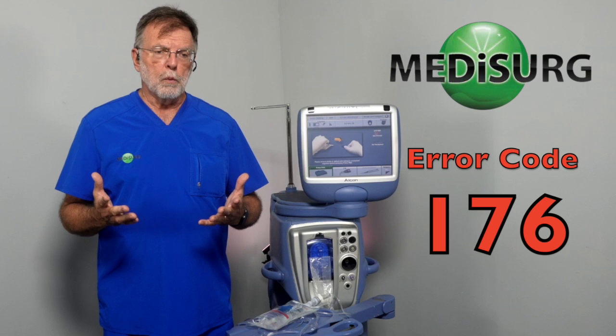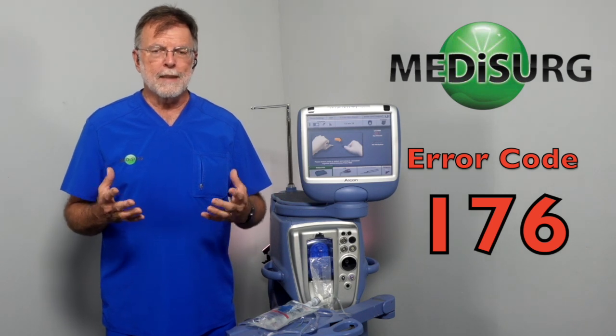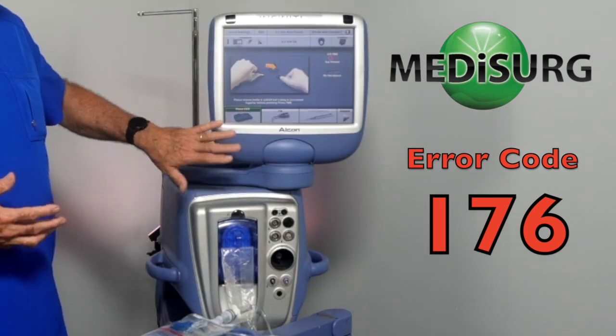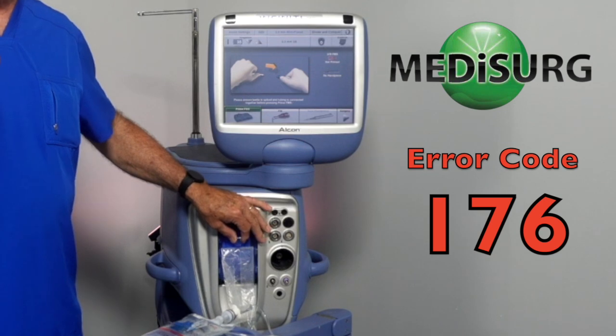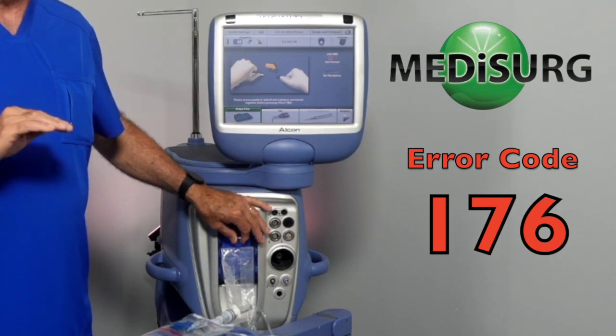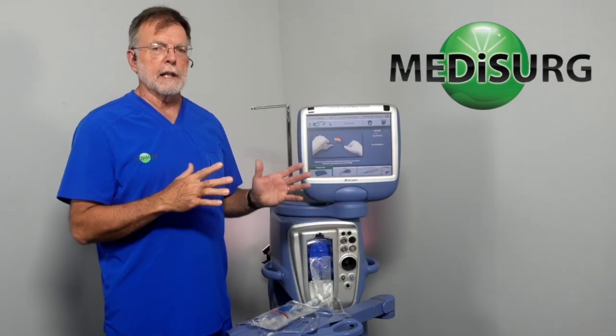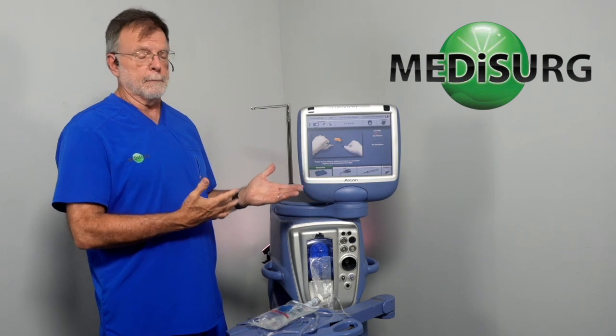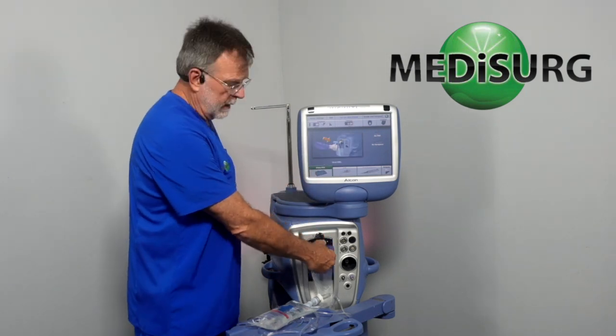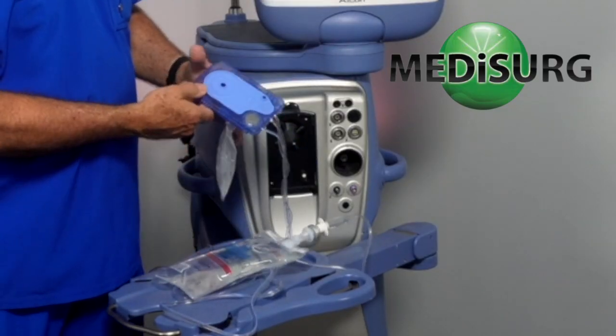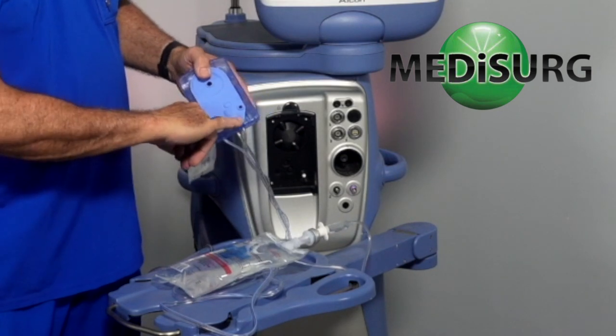So today, error code 176. This is something about the Alcon Infiniti where one of the devices that measure infusion pressure is out of calibration. I can't really demonstrate that today because it's working, but I have seen it. And what we have on the cassette are two areas where it's measuring.